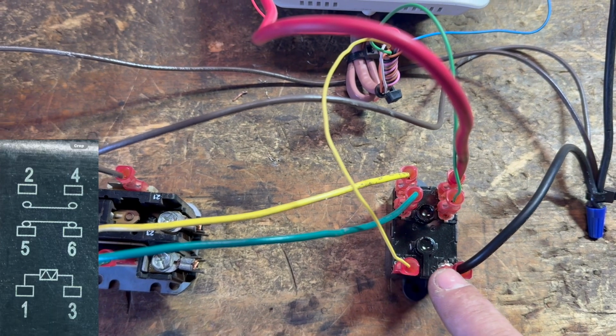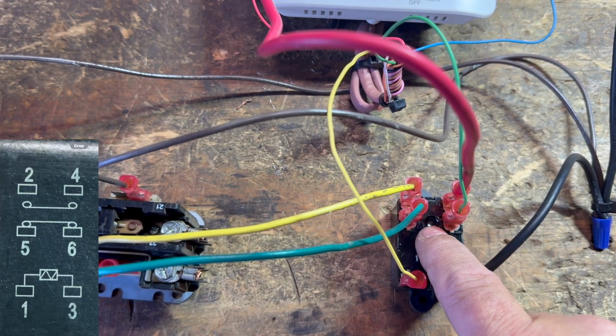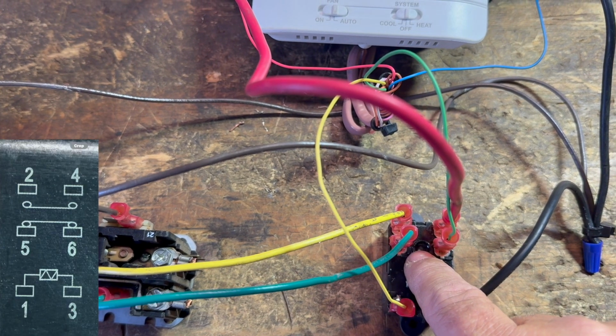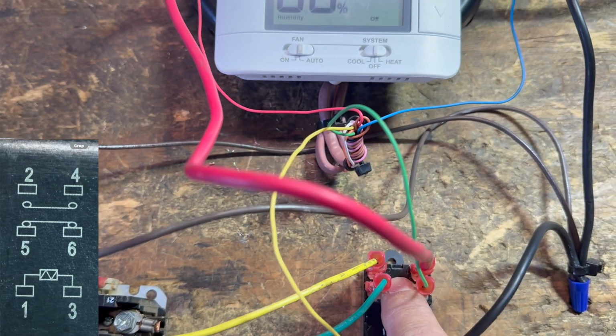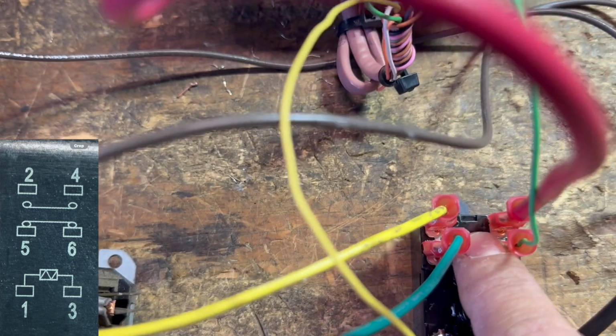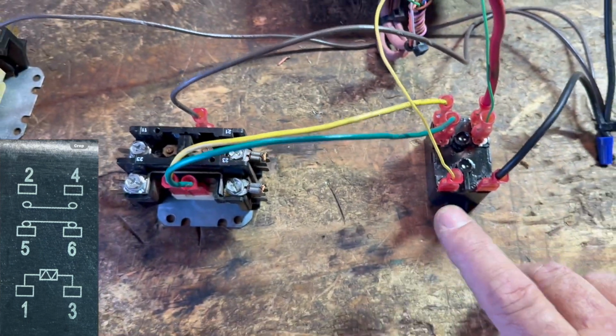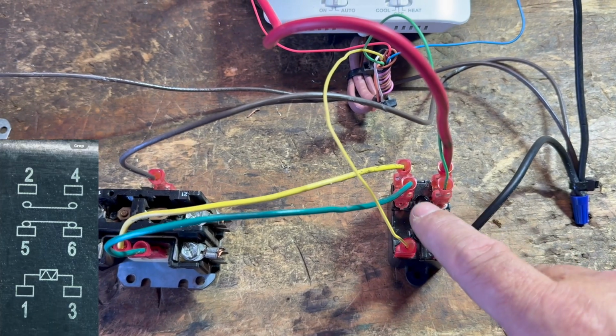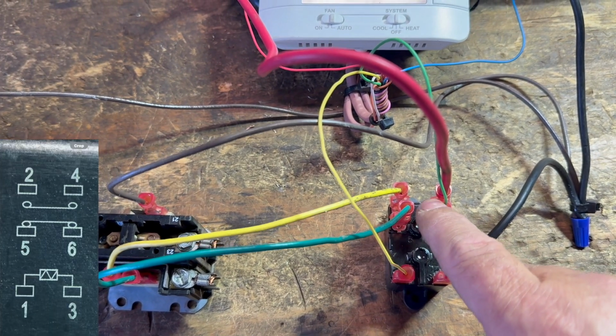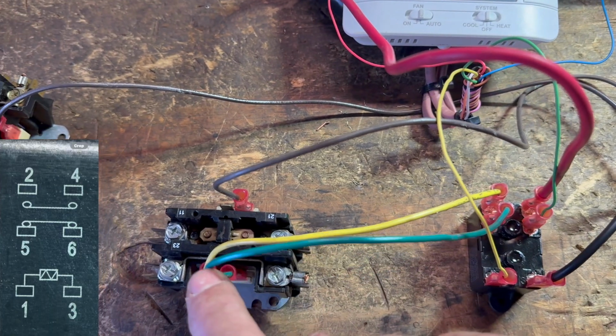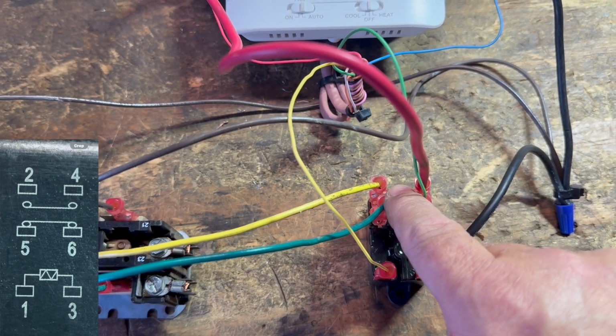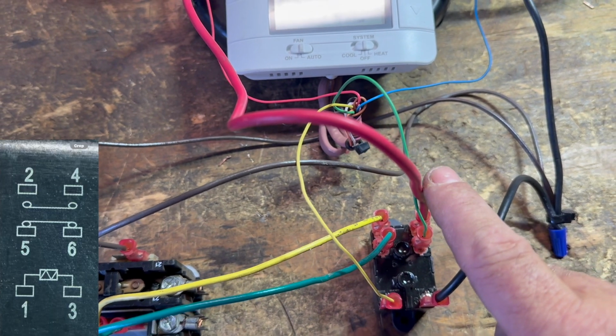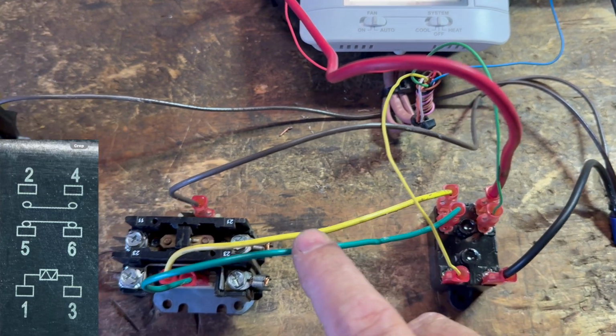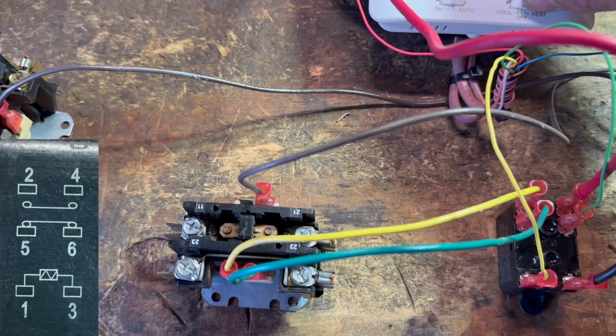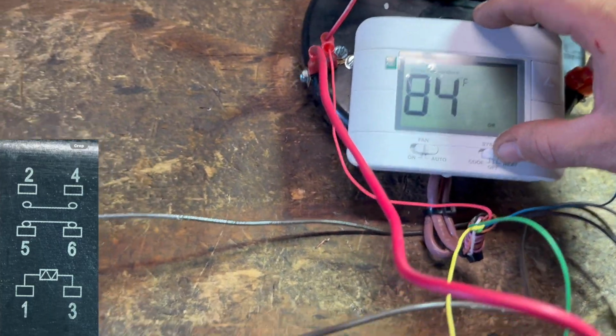Inside here is a little coil that activates a load, which changes these two terminals from normally closed to normally open, and these two rear terminals from normally open to normally closed. So when I activate 24 volts, voltage will no longer, even if it's coming in through the green, be applied through this green. It will close the back switch, taking 24 volts from this constant red and throwing it to yellow to activate. So let's go ahead and do that now. I'm going to turn it on cool, and again you'll be able to see the load activate.